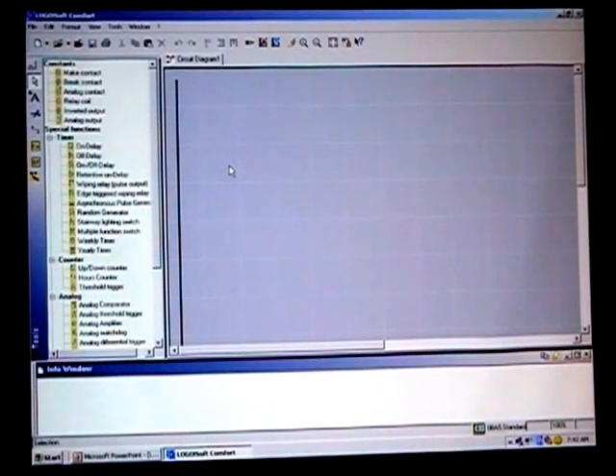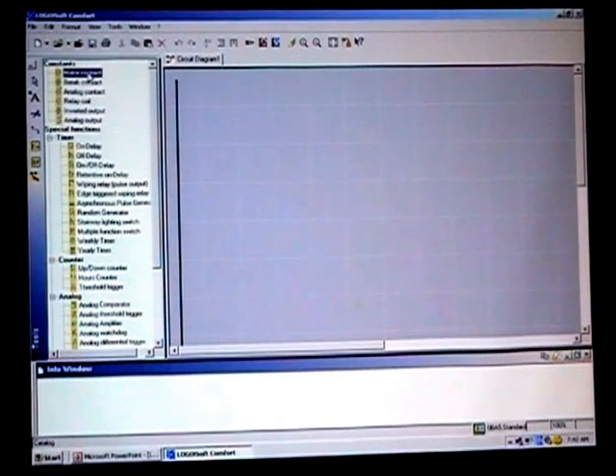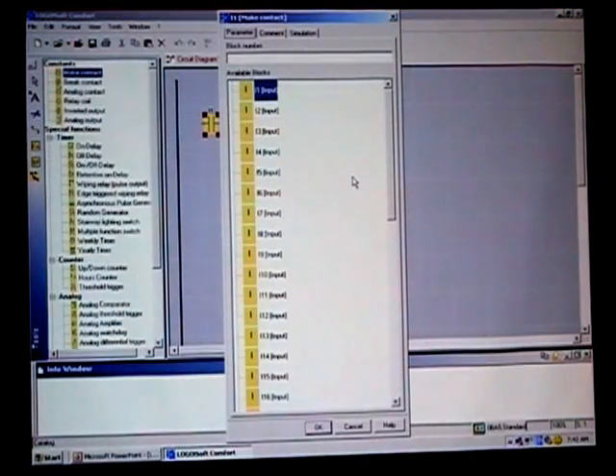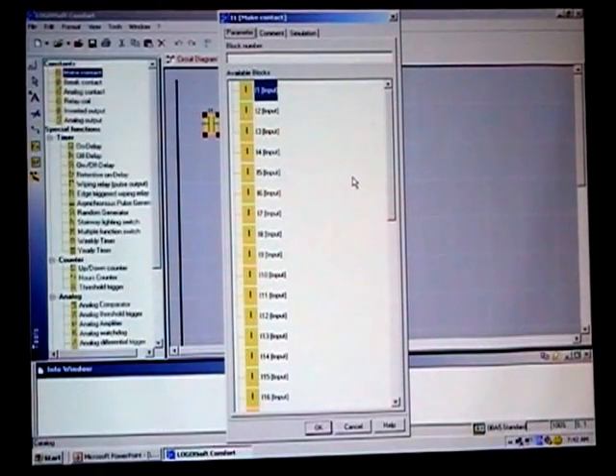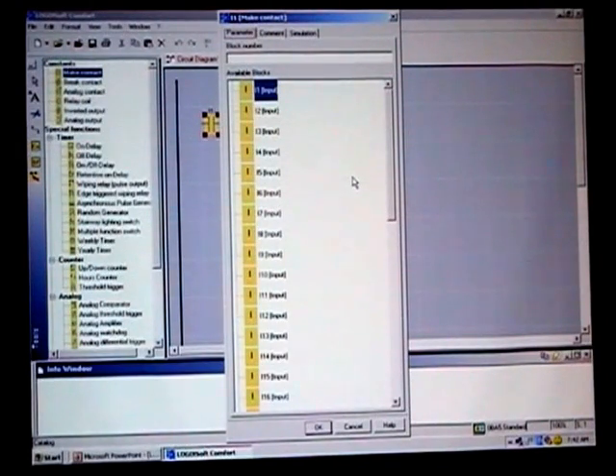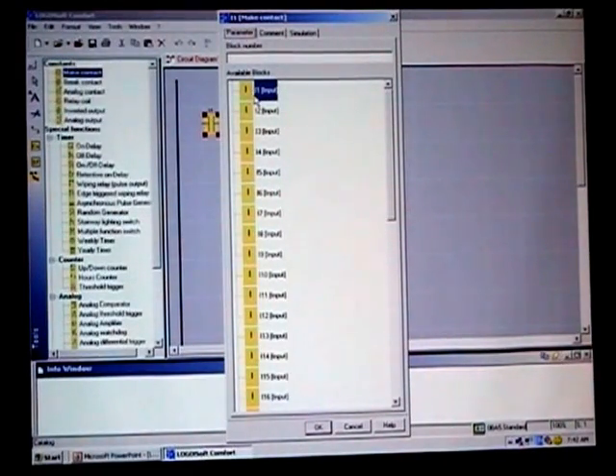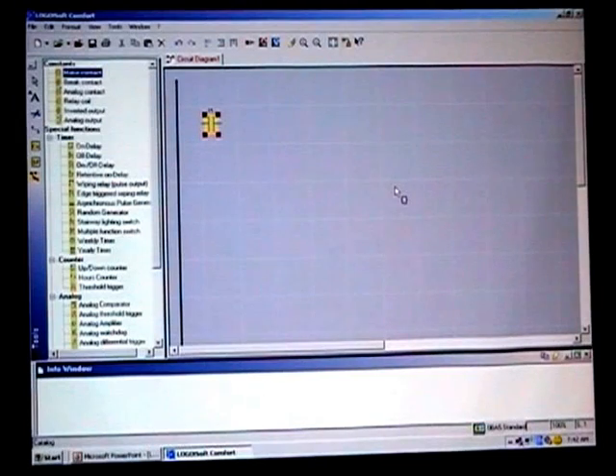The most simple thing we can do is create a make contact. Grab a make contact and drag one onto the screen. As soon as you do, it gives you a selection asking what you want to address that contact as — it could be an input, an output coil, a timer, a counter. In this case we're going to address it to input I1.